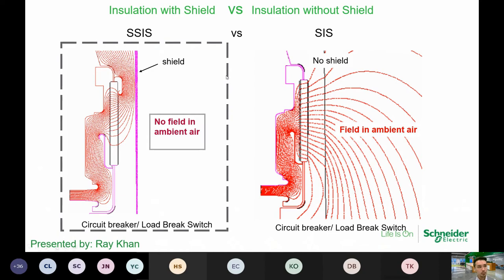With the metal shielding as well, it goes on the zero volt concept, which brings the volts to ground. Basically, on the right, you can see that without the shielding, the electrical field permeates into the ambient environment, and this is where there's potential for arcing to take place. So by having a shield, the idea is simple, but it brings a lot of safety features for the customer.